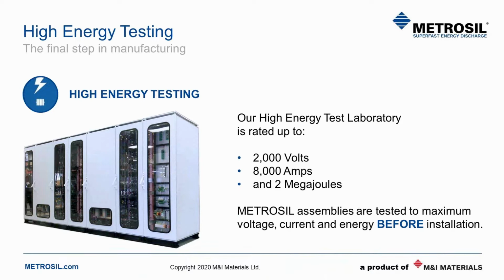This is a large controllable bank of ultracapacitors, with an internal energy storage capacity of around 10 megajoules, but we're able to discharge safely up to 2 megajoules of energy into a METROSIL unit to verify its performance. So if a customer tells us the maximum current and energy values and a protection voltage, we can demonstrate that a unit can handle this energy while keeping the voltage at or below a safe maximum.